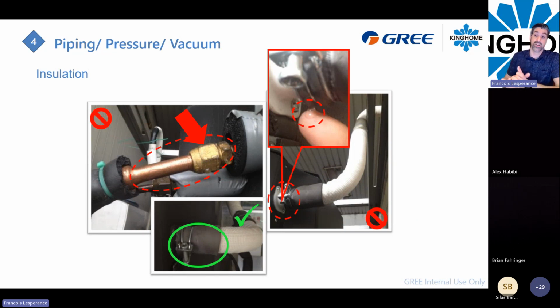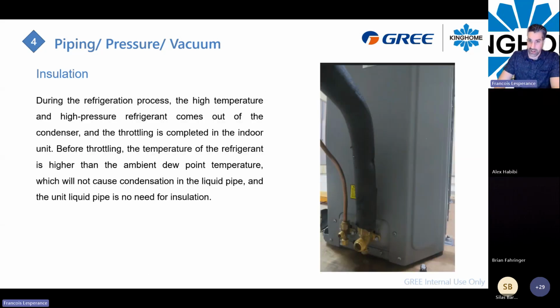The insulation, make sure you have a good insulation around the valve, around the piping, and all the stuff. Just make sure that will not create some condensate water. Same thing for the indoor unit. So make sure you will wrap the valve correctly by adding some sort of Armaflex around it. Make sure it will not condensate. Okay. And on the outdoor unit as well, you can push your Armaflex around the valve here. But yeah, for sure, at the outdoor unit, maybe that will condensate a little bit, but at that point, it's normal.